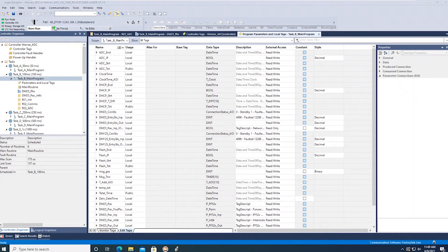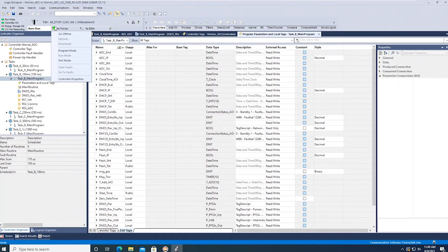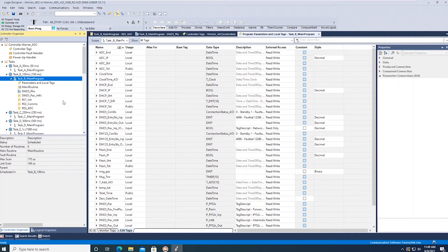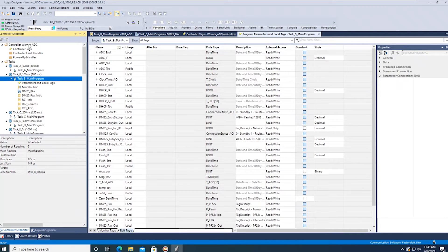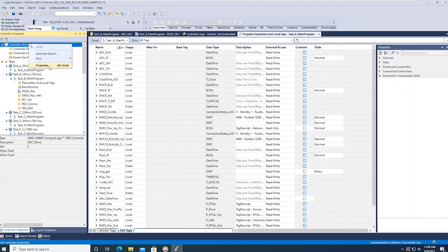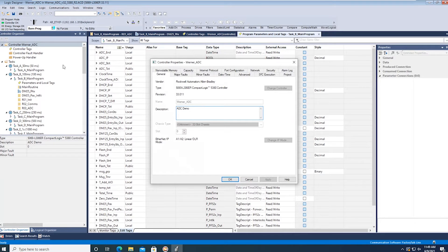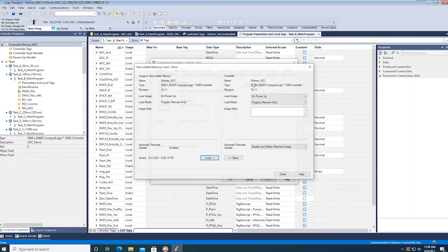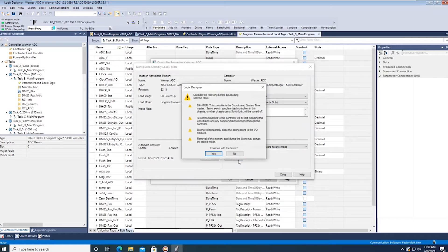To activate Firmware Supervisor, put your control into program mode and then right click on the controller in your I/O tree and click Properties. In the next window, click Non-Volatile Memory. Select the Load/Save button, then Load Image on Power Up and enable Automatic Firmware Update. Click Store, then Yes to continue with the store.